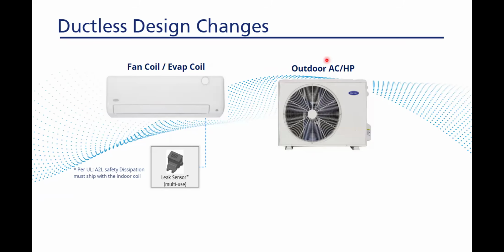Ductless is a little bit different because ductless always is communicating. The indoor and outdoor unit always talk to each other. Nobody makes non-communicating ductless anymore, and it's not for decades. So they're always communicating. So there is no leak board on there. There's no dissipation board. There's just a sensor that plugs into the regular board that's already in there, and that board has software in it that tells the outdoor unit to shut off and the indoor fan to turn on.